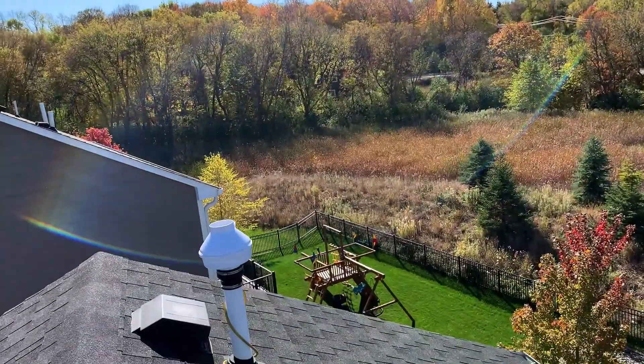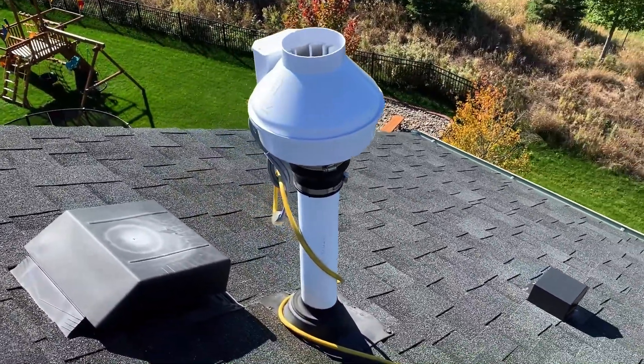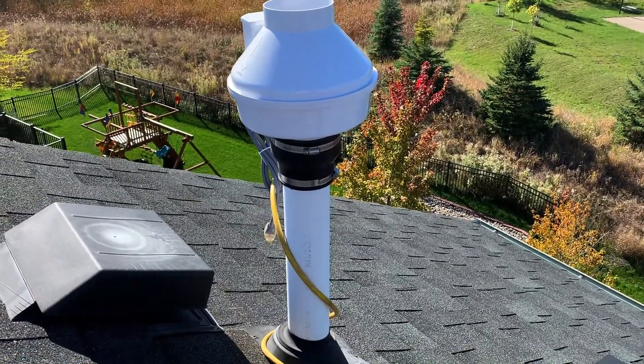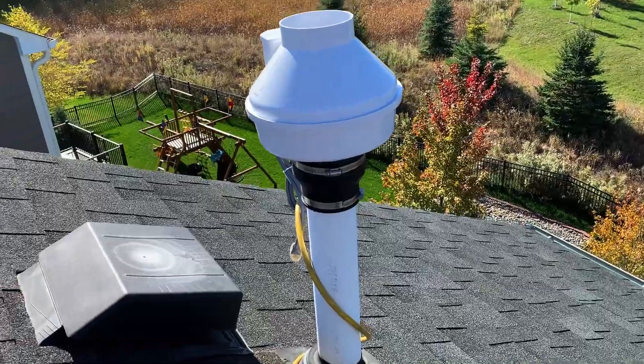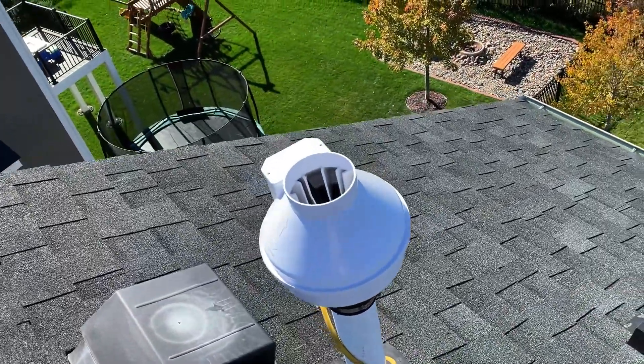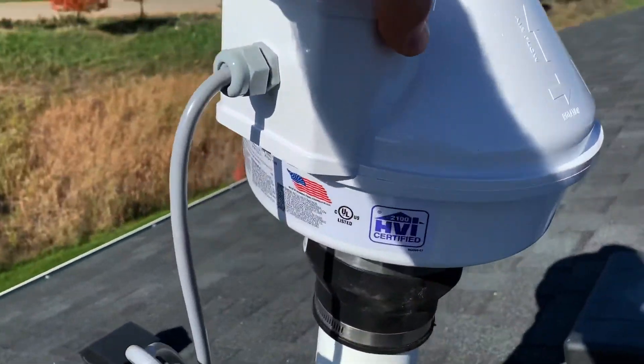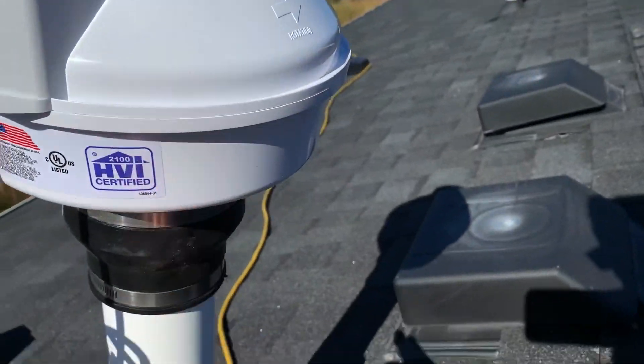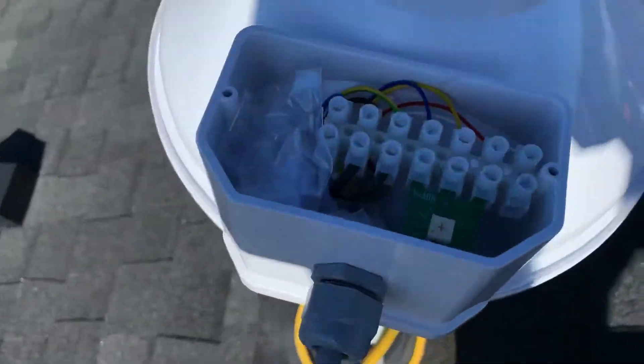Up on the roof here, we've located where the passive pipe comes out through the roof. It goes straight down two stories into the basement and into the concrete. It's not tied into the sump basket or sump cover, which is pretty common here. So I've added this Fantech RN2 EC fan — here it is, temporarily running off a cord, set to 50 percent.